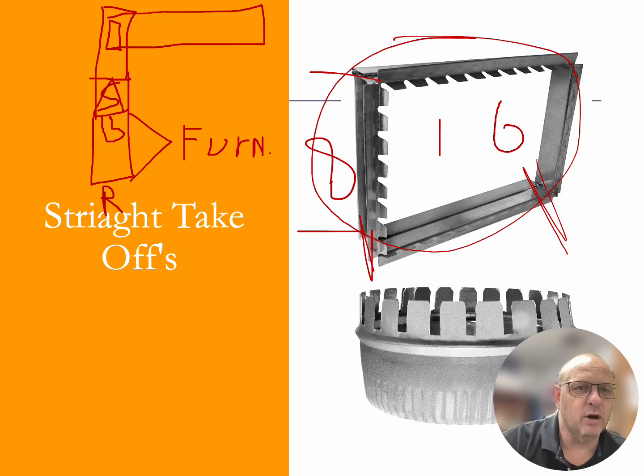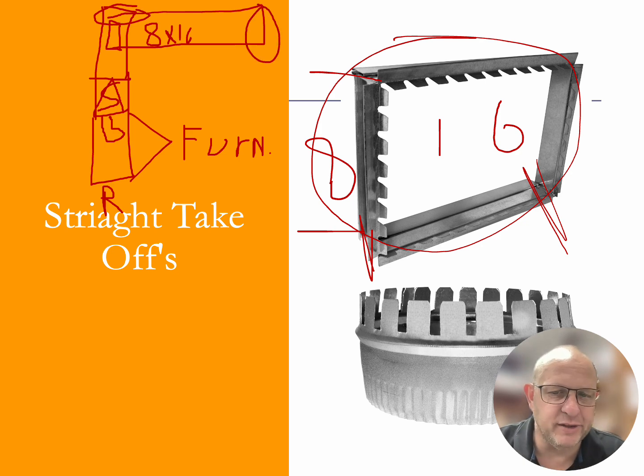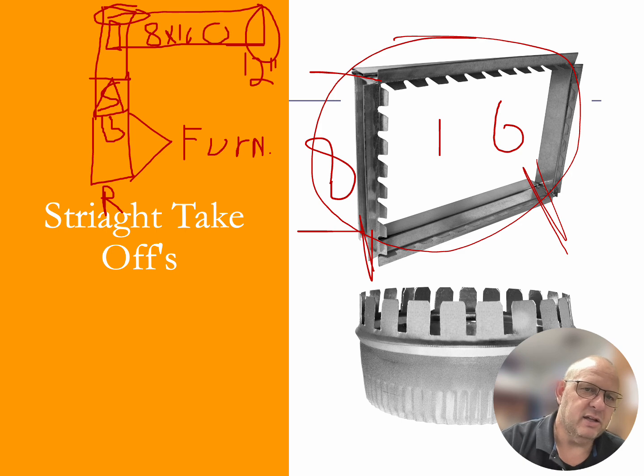Now, within this ductwork right here, which happens to be an 8 by 16 duct, we are going to put other takeoffs into that ductwork as well. A couple of rules that we have to understand about this ductwork. We are not to put takeoffs at the ends of our piping, because we have something called static pressure, total pressure, and velocity pressure that we need to build up within this ductwork so that we can distribute the air correctly over the entire thing. So we would come back 1 foot off of the ductwork at the end of it, at least 12 inches. And then we would put what we call another takeoff.